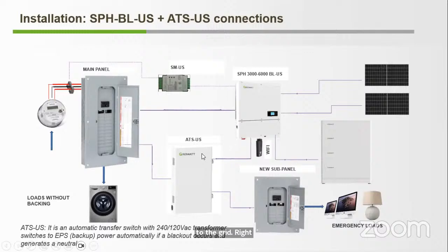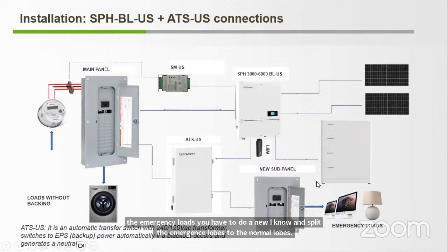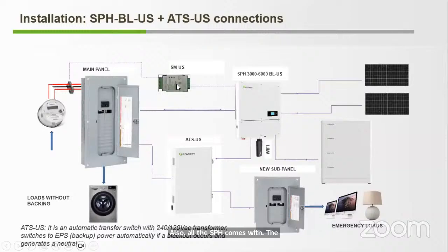So this model needs to be connected with the ATS US. This ATS US is an auto transformer to have the split phase, right? In the grid port, you can connect directly with the grid, but for the emergency power supply, it's mandatory to have the ATS US. For the emergency loads, you have to make a new sub panel and separate the emergency loads from the normal loads. Also, all the SPH comes with the SMUS meter, right? If you want to do zero injection, you can connect the CTs in the lines and connect the meter to the inverter and start doing zero injection.